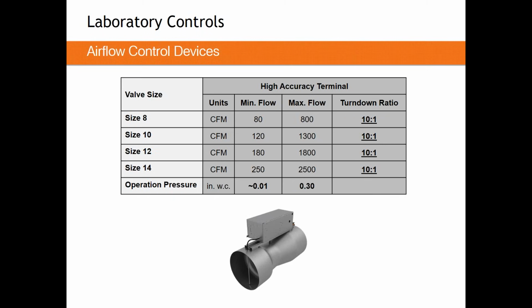So generally speaking, and this is just a rule of thumb, it's not a hard answer to any of life's questions here, but if you have 0.5 inches, if you have half an inch of pressure across any valve size, you can get anywhere from minimum flow to maximum flow, and you can control that airflow. So I generally recommend about a half an inch of pressure drop is what you should plan for a high accuracy terminal in your system. It'll give you good controllability, or at least some controllability, and a full range of airflows that are available.